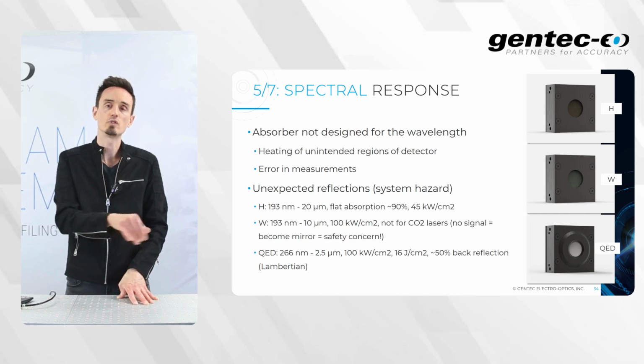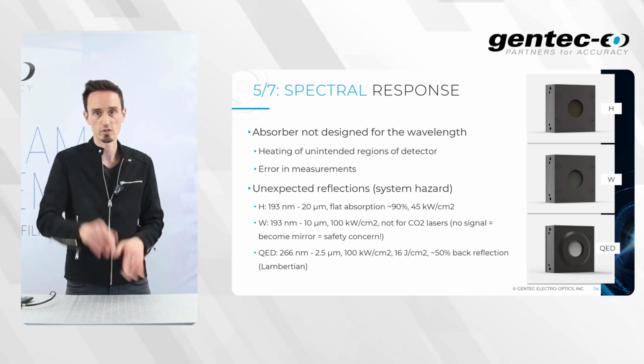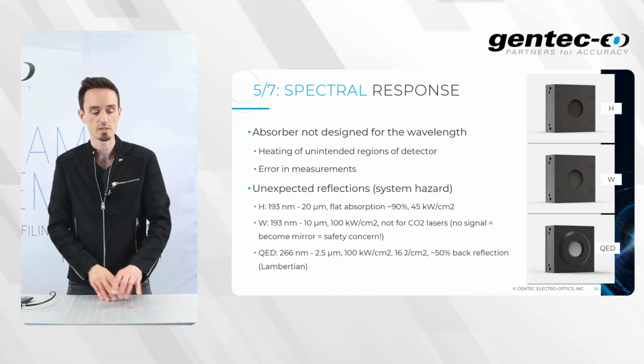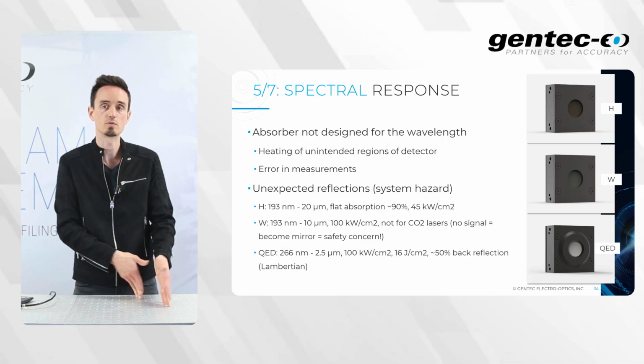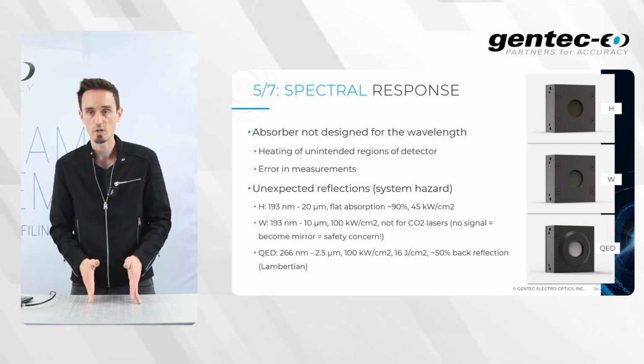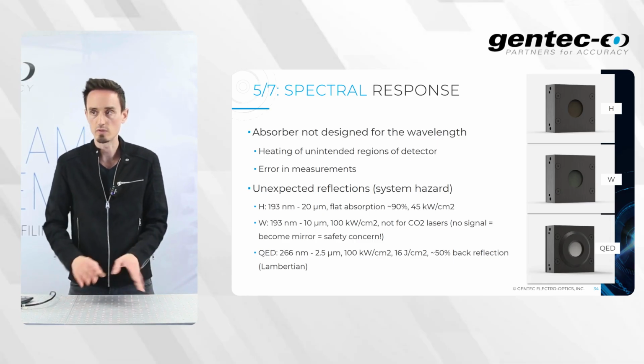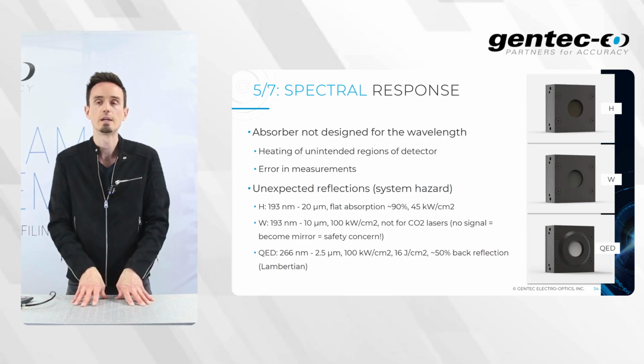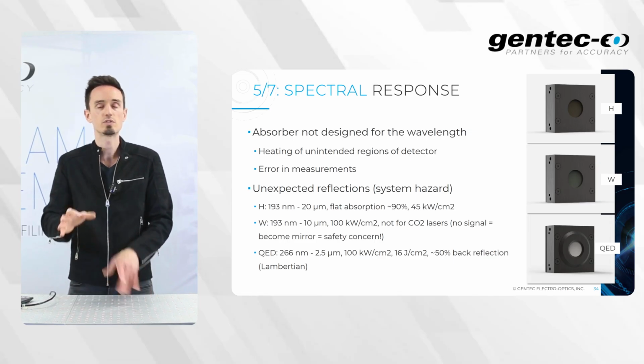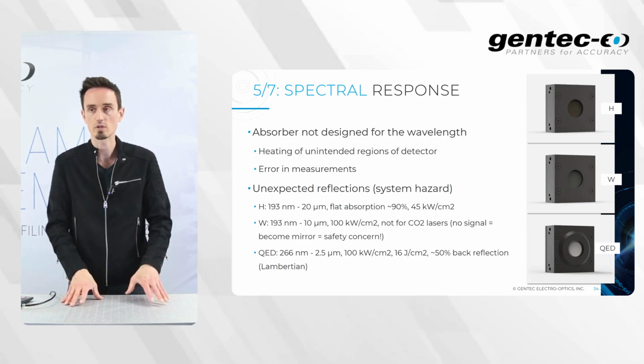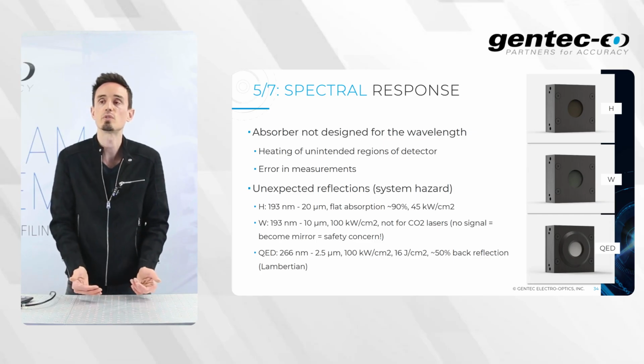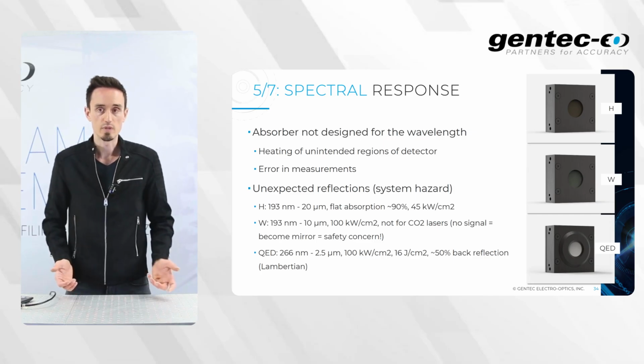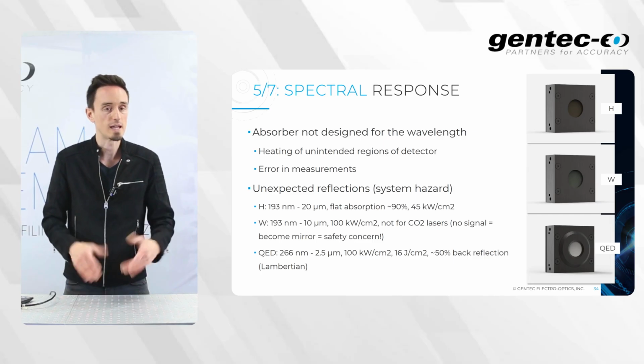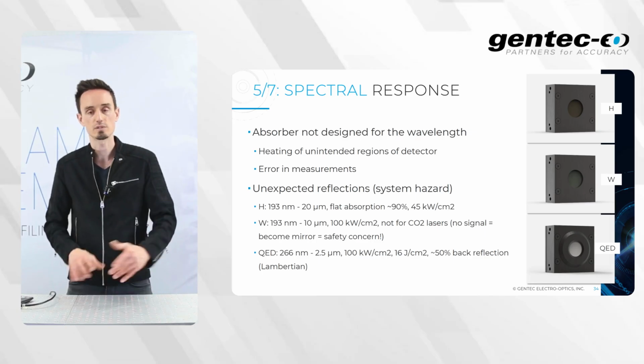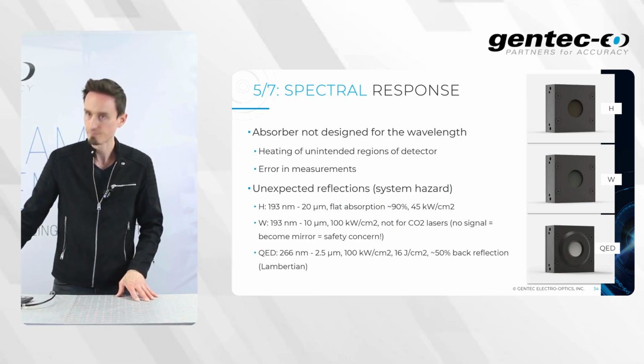And then if you take the last one, the QED attenuator in front of, in this case, the thermopile detector for power measurements, it goes from 266 nanometers up to 2.5 micron for calibrated measurements. You could extend a little bit down in UV or potentially IR, but that's the specification. Up to 100 kilowatts per square centimeter, 16 joules per square centimeter, great damage thresholds, but it is designed to provide a 50% back reflection level. Lambertian, diffuse, but that has to be taken into account in your system design and considerations.